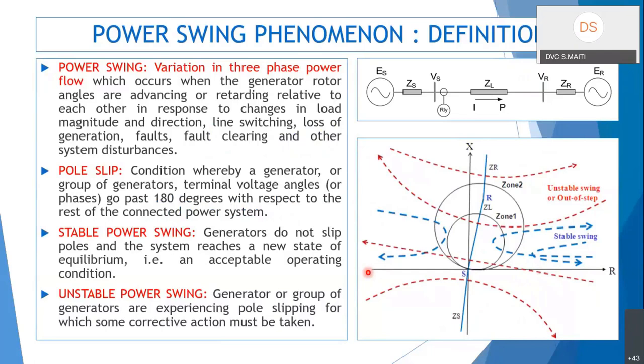A power swing is a variation in three-phase power flow which occurs when generator rotor angles are advancing or retarding relative to each other in response to changes in load magnitude and direction, line switching, loss of generation, excess load, fault happening, fault clearing, and other similar system disturbances.